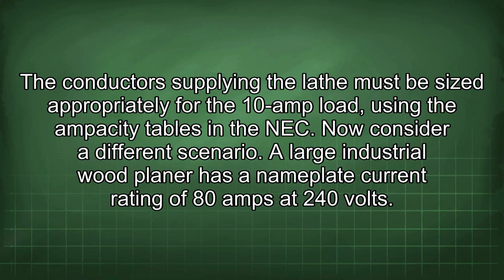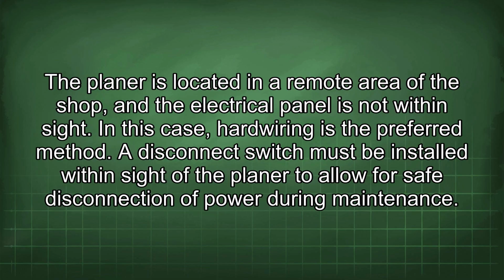Now consider a different scenario. A large industrial wood planer has a nameplate current rating of 80 amps at 240 volts. The planer is located in a remote area of the shop, and the electrical panel is not within sight. In this case, hardwiring is the preferred method. A disconnect switch must be installed within sight of the planer to allow for safe disconnection of power during maintenance.